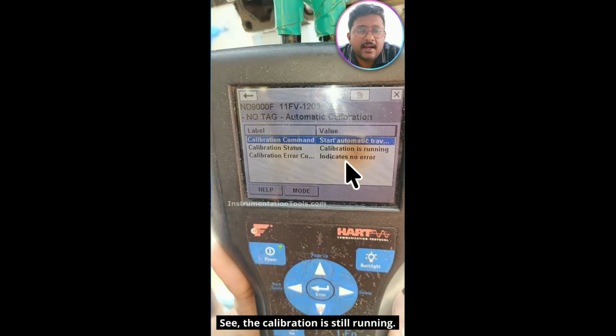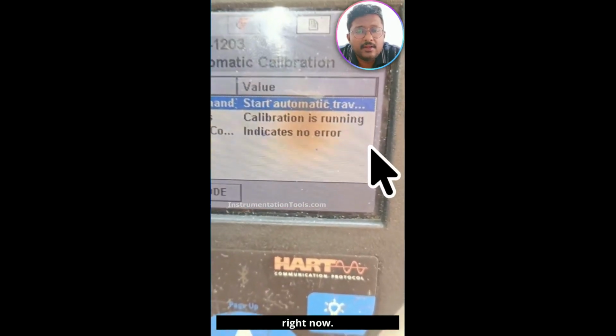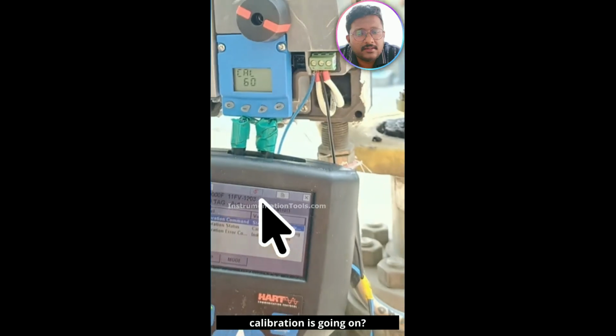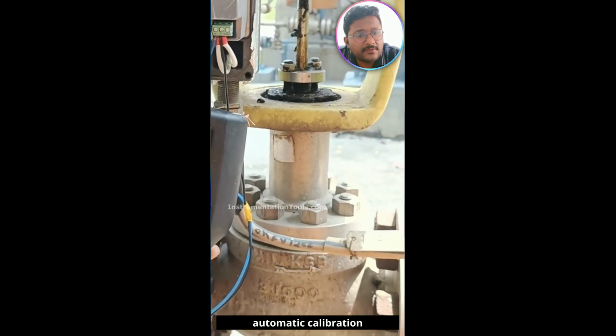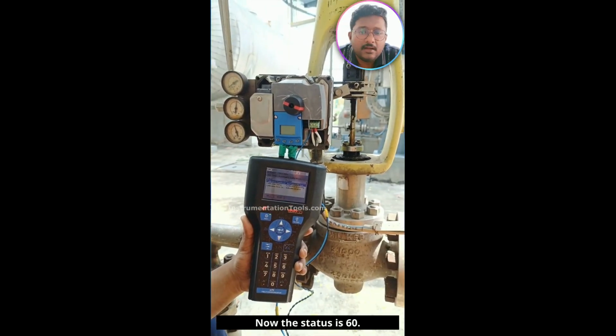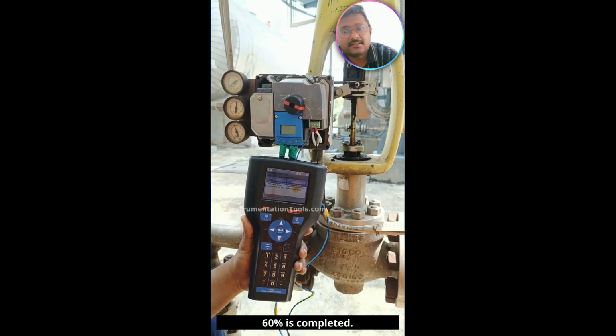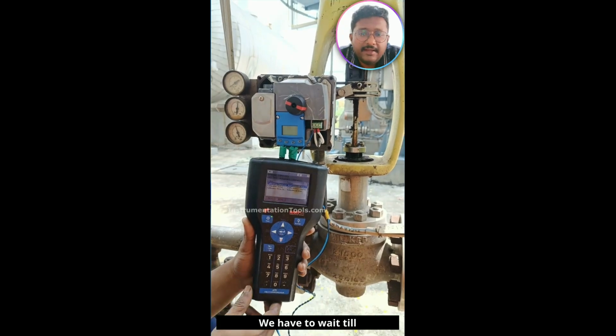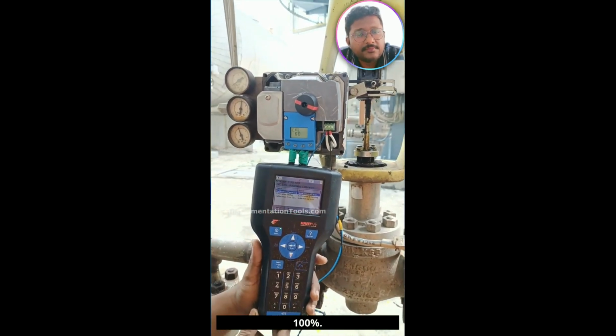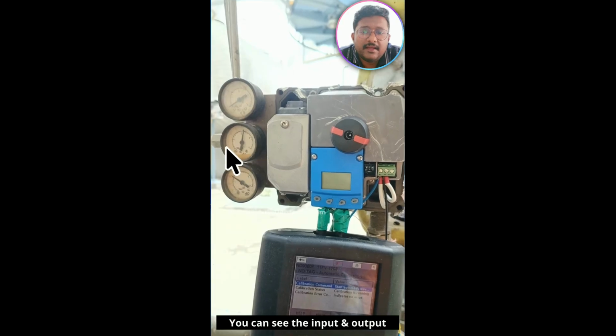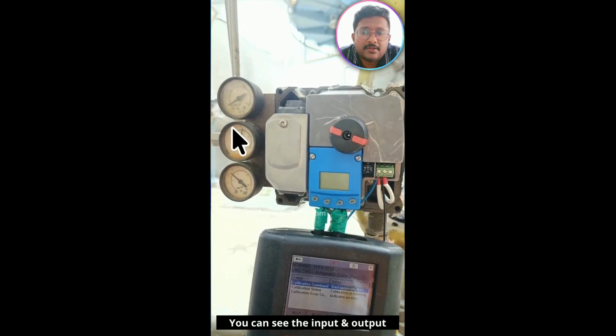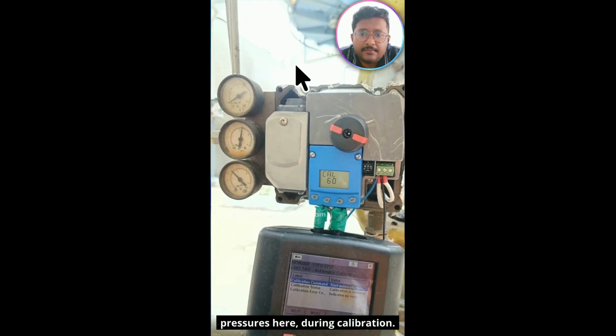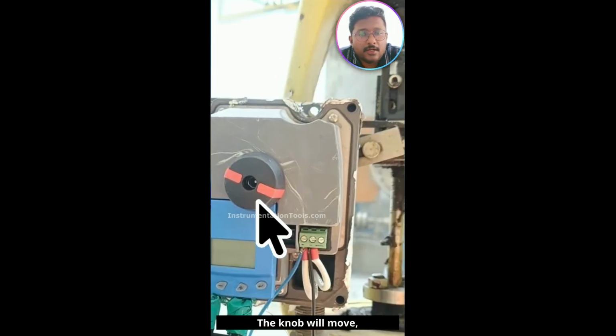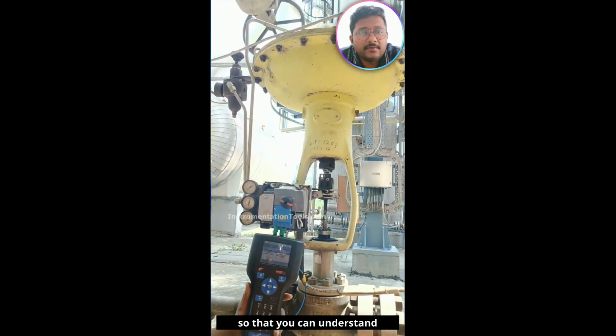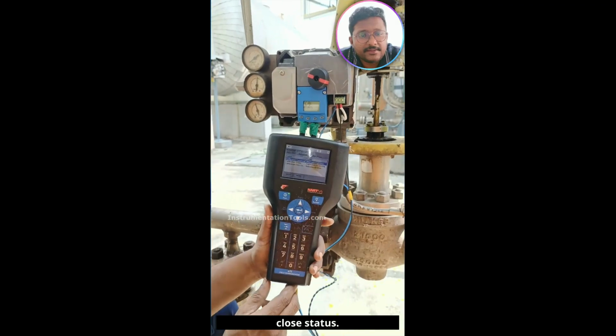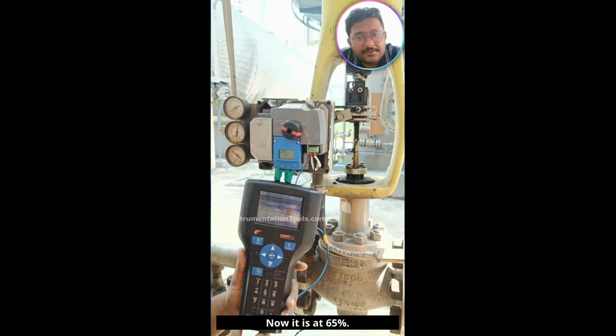See, the calibration is still running. There are no errors right now. What type of calibration is going on? Automatic calibration plus position feedback adjustment. Now the status is 60. 60% is completed. We have to wait till 100%. So these are the pressure gauges. You can see the input and output pressures also here during the calibration. You can also see this knob. The knob will move so that you can understand the valve open or close status. Now it is at 65%.